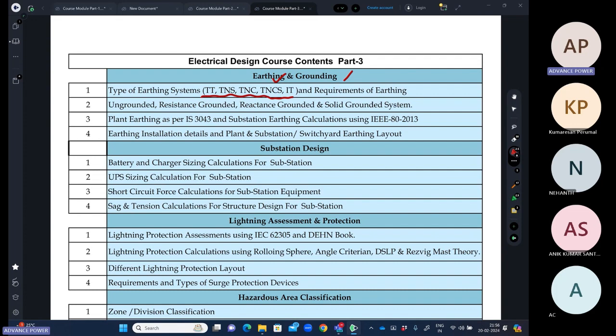So you'll be able to know that during a fault, all these earthing systems will behave differently. Sometimes we require a resistance grounded system. You might have studied high impedance grounding and low impedance grounding also. We'll discuss why we use the NGR, why we use the NGT in the system, and why we sometimes use the ungrounded system. What are the benefits and disadvantages of these systems, we'll discuss in detail.